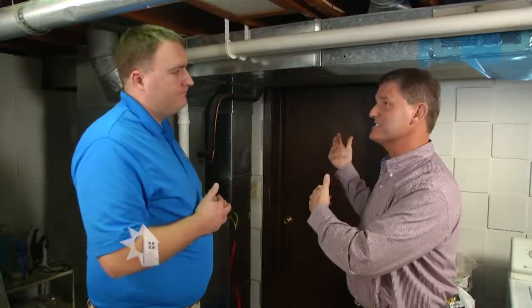Now, what if someone says they need to get in and really clean inside — do you recommend that, like with brushes? If you change your furnace filter regularly, you're never going to need to get inside and clean your ductwork. Aside from that, the brushes used to clean ductwork can actually score the inside of the ducts and increase the surface area, which actually decreases airflow and is going to adversely affect your system efficiency — doing more harm than help in that situation.